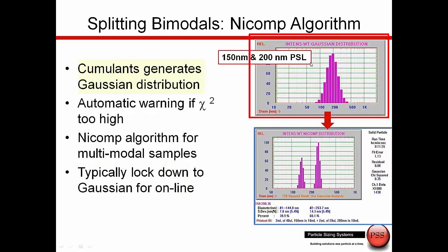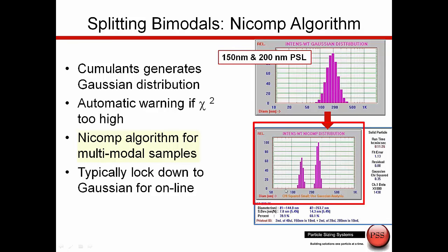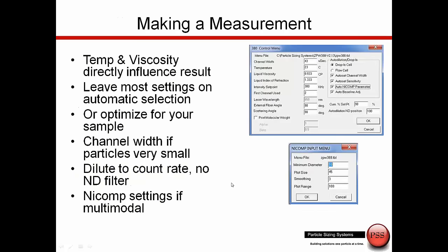When we use a Gaussian distribution, as you see here, there's a single peak and the distribution is symmetric. This particular sample, though, was a mixture of two polystyrene latex samples — 150 and 200 nanometer PSL particles — where we would need to use the Nicomp distribution to split those two peaks. That's one of the highlights of the Nicomp system, this Nicomp algorithm. We need to choose beforehand whether there's one or two peaks, and then lock this down during the measurement, because we need easy data interpretation if we're going to use this as a process monitor.